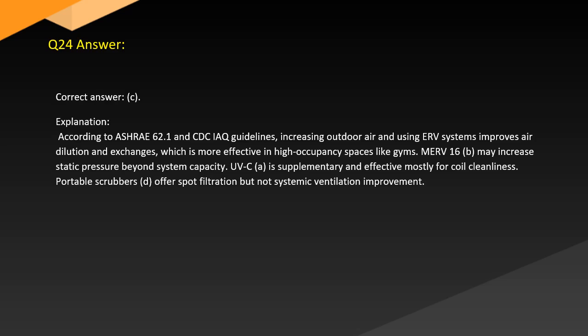Answer. Correct answer C. Explanation. According to ASHRAE 62.1 and CDC guidelines, increasing outdoor air and using ERV systems improves air dilution and exchange, which is more effective in high occupancy spaces like gyms. MERV 16 (B) may increase static pressure beyond system capacity. UV (A) is supplementary and effective mostly for coil cleanliness. Portable scrubbers (D) offer spot filtration but not systemic ventilation improvement.